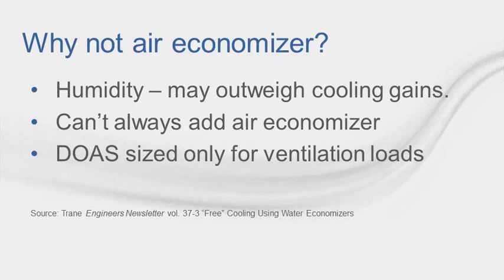Not all air handling units can be equipped with economizers due to space constraints, distance to the outdoor air intake, increased return or exhaust fan sizing, duct sizing or routing, or other application-specific constraints. Dedicated outdoor air units are typically sized to handle only the ventilation loads, so full cooling capacity cannot be achieved by an air-side economizer. Now let's talk about some different types of waterside economizers and how to model them in TRACE 700.